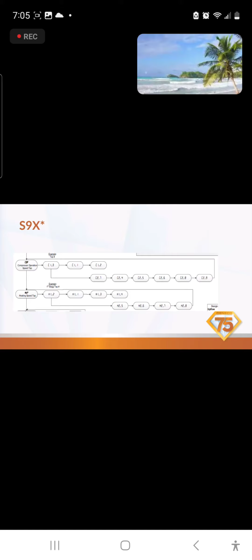On the S8X, it's very similar. As you can see here, we only have a single stage AC and a single stage heating, and the bars down there only have 1 row, so you only have 1 speed to set. If you have 2 stage though, you set the first stage. Once you set that, it kicks you into the second stage, and as you can see, on the cooling it says C1 for speed taps 1, 2, 3, and C2 for 4, 5, 6, 7, 8, 9. That's saying cooling stage 1 and cooling stage 2. The same is set there for heating stage 1, heating stage 2. It'll say H1 and then your speed tap. It'll say H2 and then your speed tap. So you know which one you're setting.